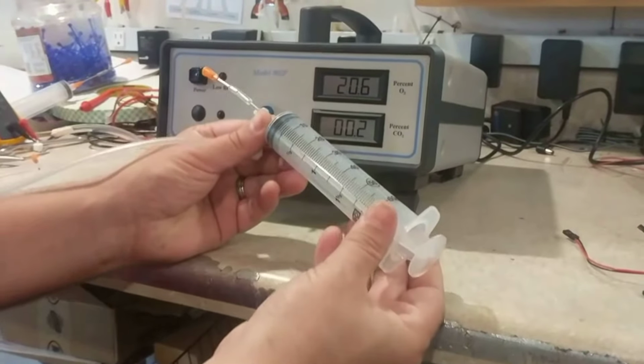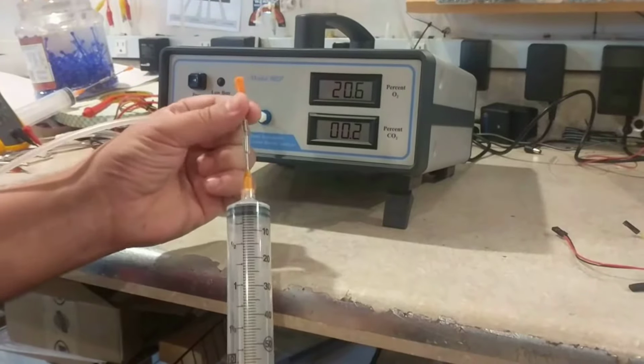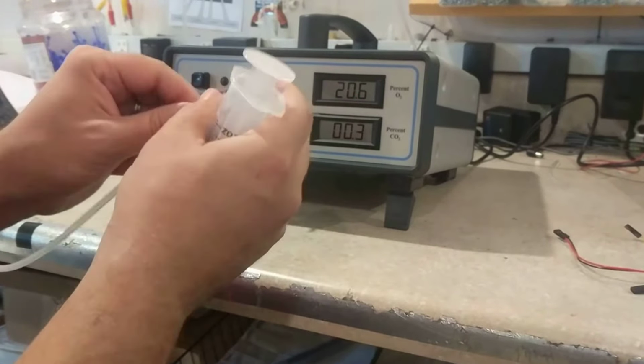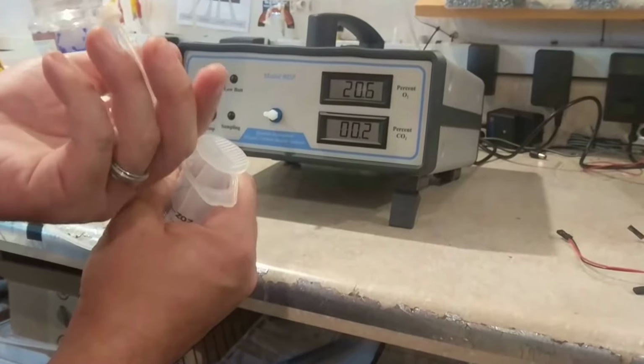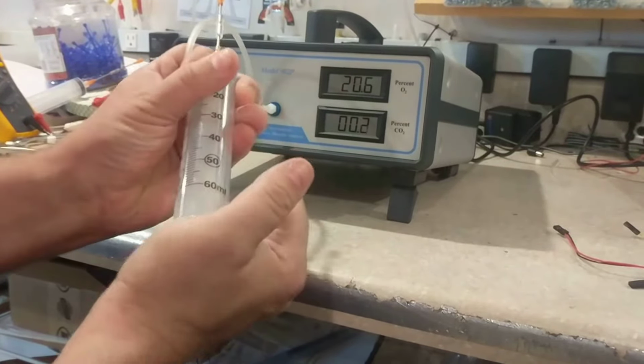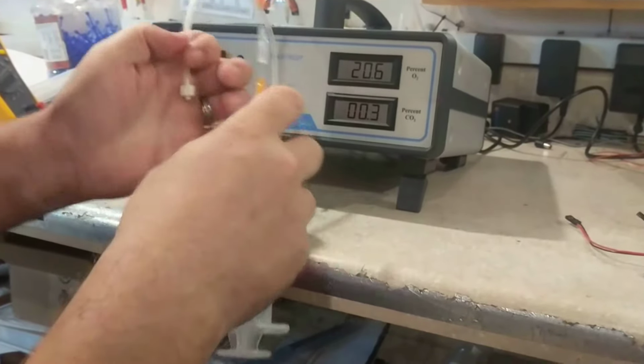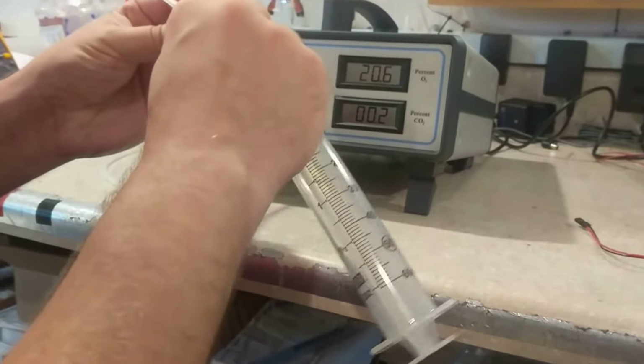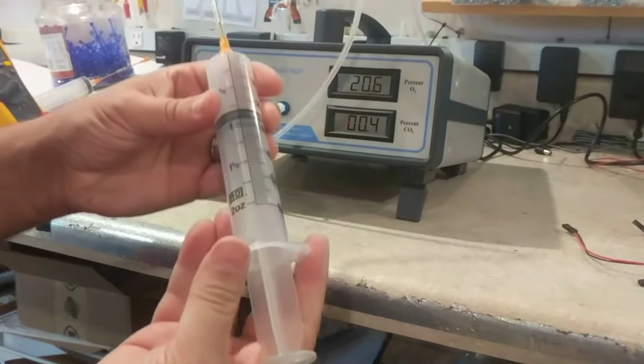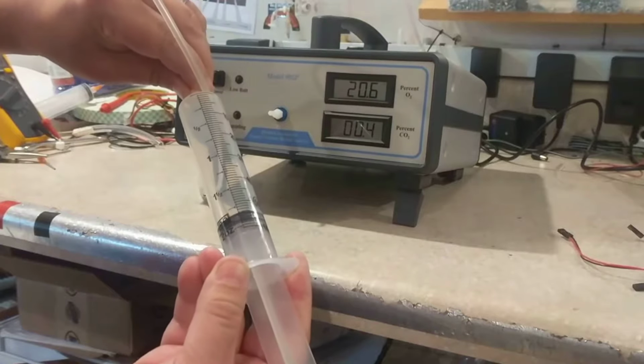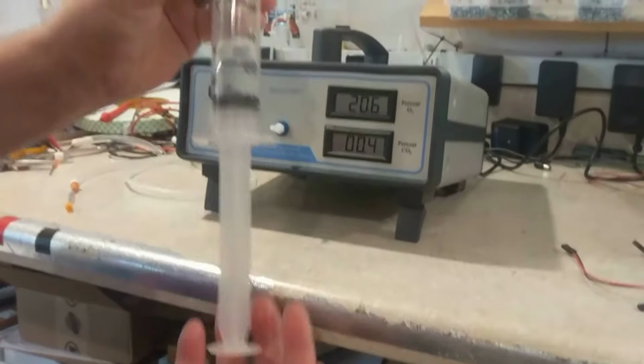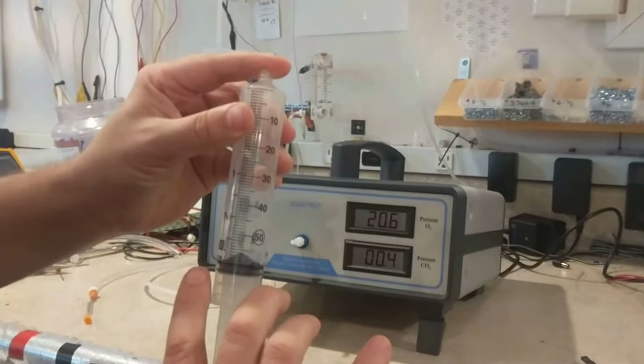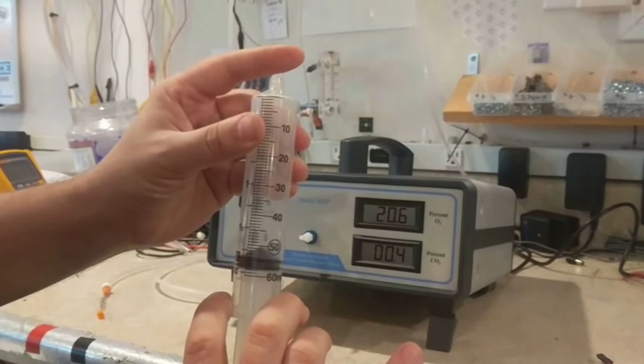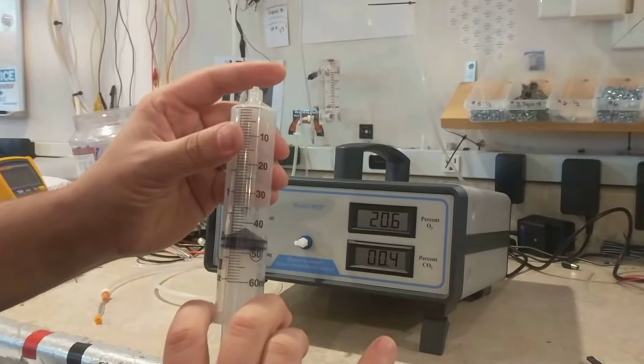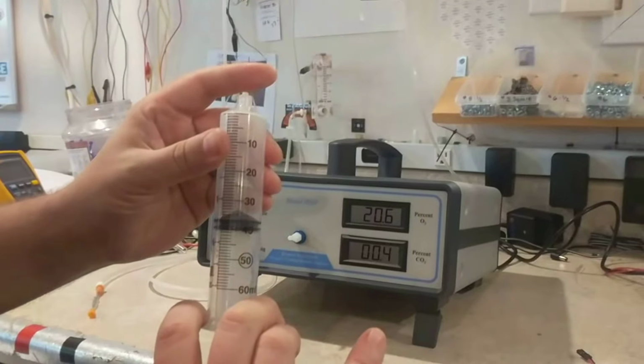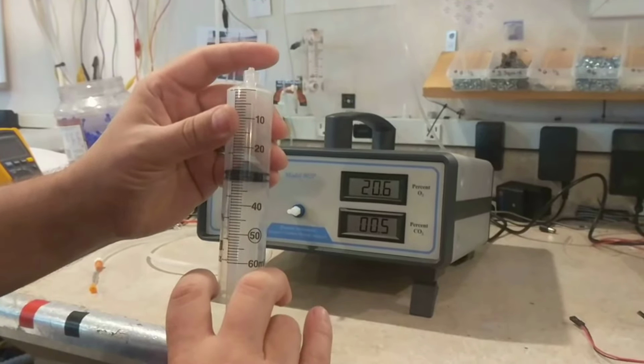So what we're going to use today is a 60 cc syringe with a double orange connector. Out of this tube I have flowing pure CO2 at the moment. So what we're going to do is we're going to check the 16.66% level. So the first thing I'm going to do is fill the syringe with pure CO2, and then I'm going to evacuate all but 10 cc's of the syringe.